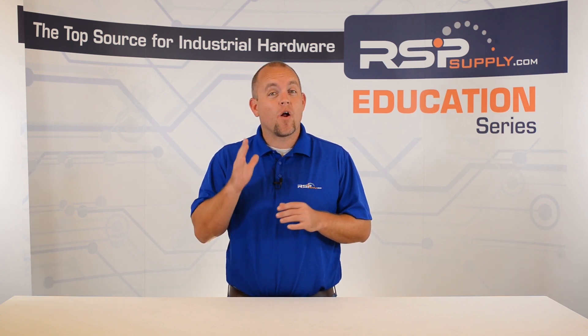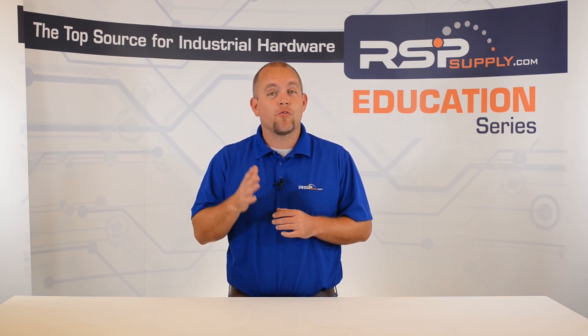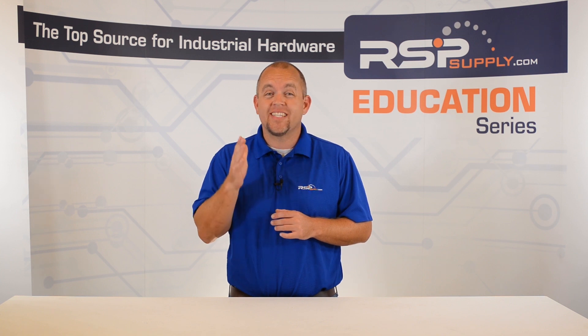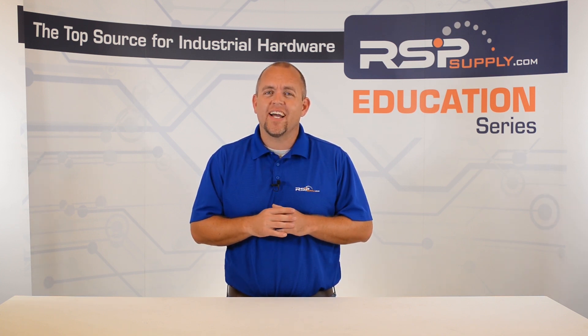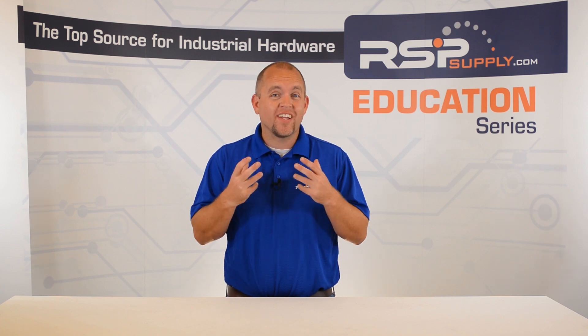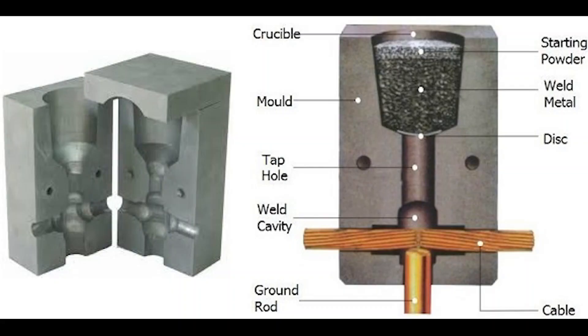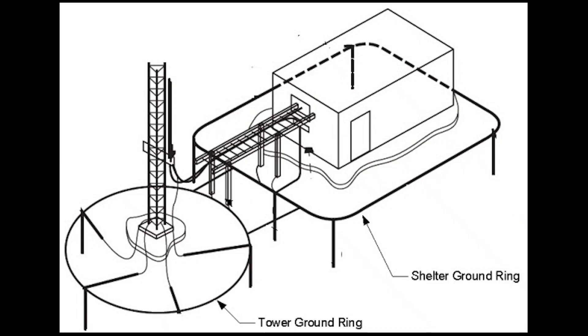It is always recommended that where the grounding electrode conductor meets the metallic tower structure, that the same special welding technique be used. This welding technique is referred to as exothermic welding. The best system to use for grounding a tower is to install a ground ring. As mentioned in some of our previous videos, a ground ring is a system of conductive grounding material that will encircle the tower.